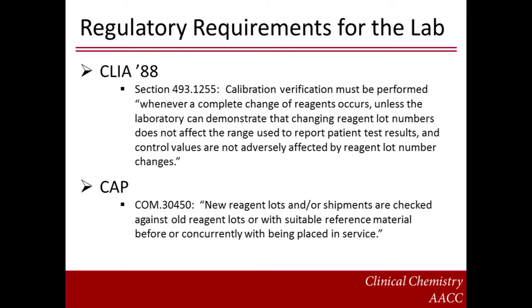Manufacturers generally attempt to minimize reagent lot variation through stringent manufacturing processes by conducting lot release testing prior to the distribution of a new reagent lot. In turn, most clinical laboratories also perform lot-to-lot validation testing in order to verify manufacturer claims and to ensure consistency in patient results.